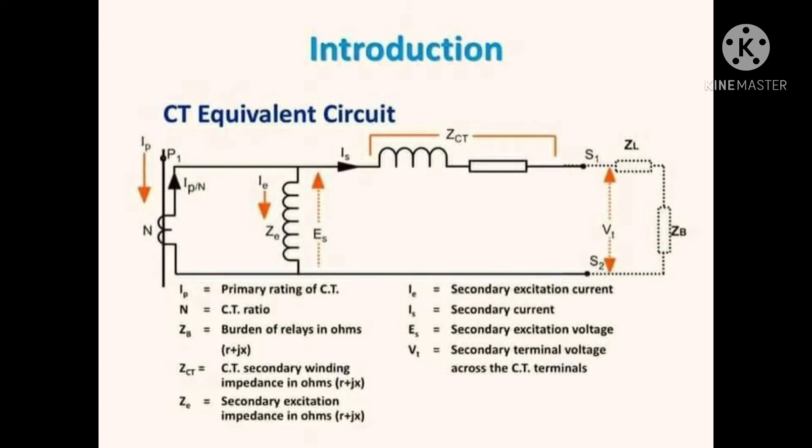Equivalent circuit of CT: the total impedance on the secondary side is the sum of relay burden, lead wire resistance, and leakage impedance of secondary winding. Therefore, the voltage developed in the secondary winding depends upon these parameters directly.